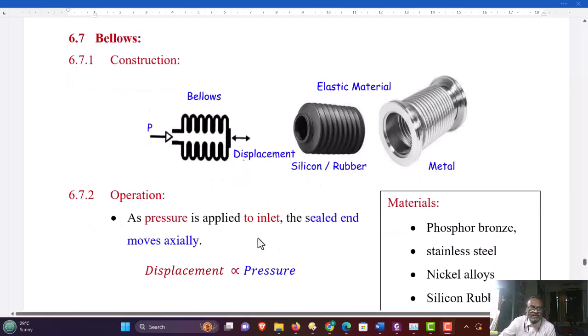The operation is very simple. Here this tube is sealed at one end and the other end has a connection for the pressure fluid. The sealed end can freely move under the application of the pressure. When the pressure is applied to the pressure port, the bellow will be stretched and the sealed end moves. The applied pressure decides the displacement of the moving end. This displacement can be further measured by using any displacement sensor. One of the applications we have seen in the capacitive sensor.